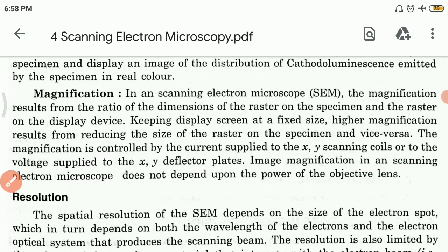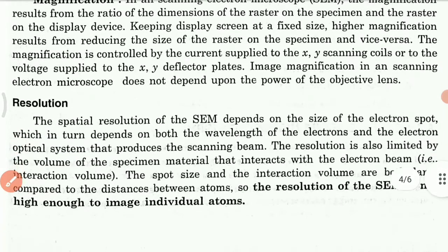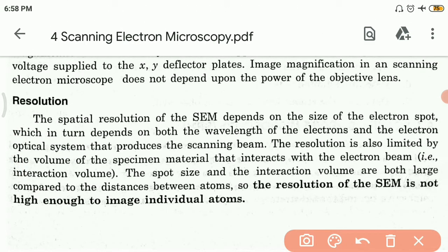The spatial resolution in SEM depends on the size of the electron spot focused by the condenser lenses. This in turn depends on both the wavelength of electrons and the electron optical system producing the scanning beam. The resolution is also limited by the interaction volume, that is, the volume of specimen material which interacts with the electron beam.